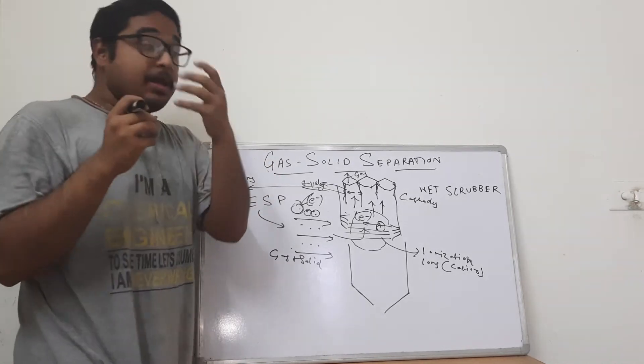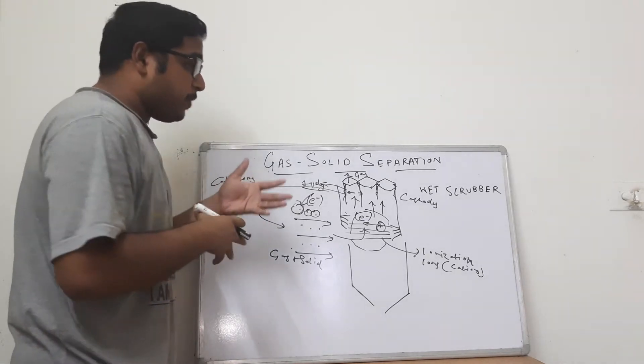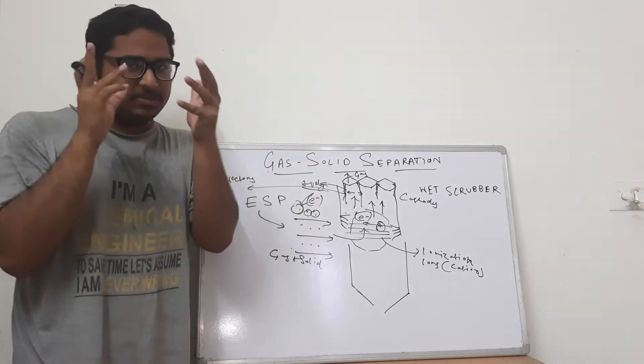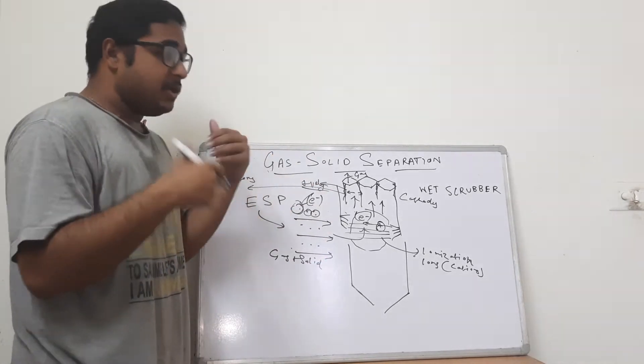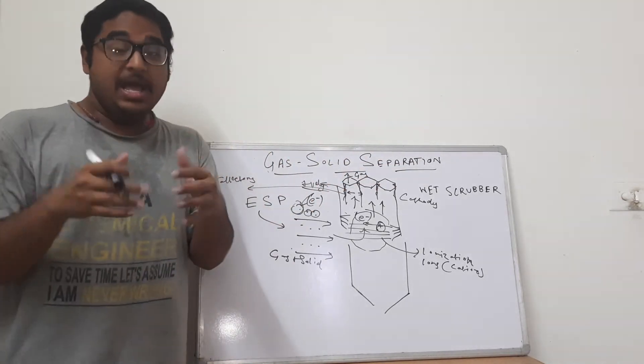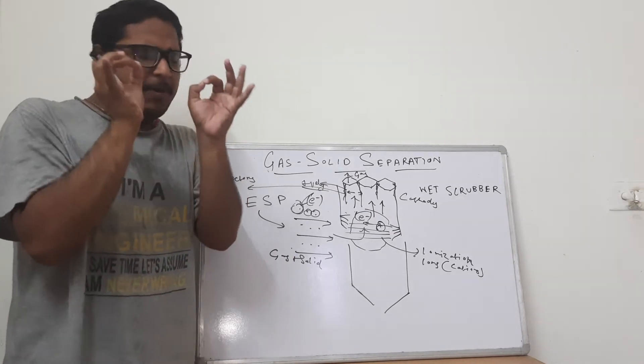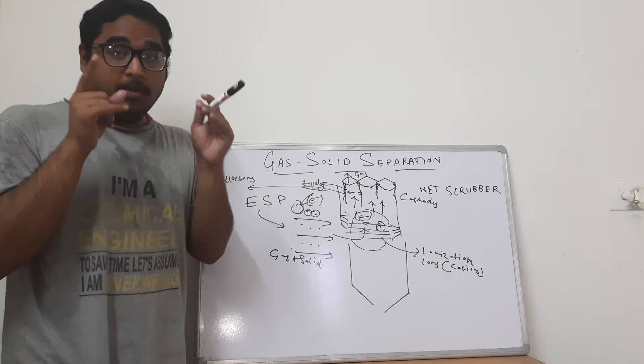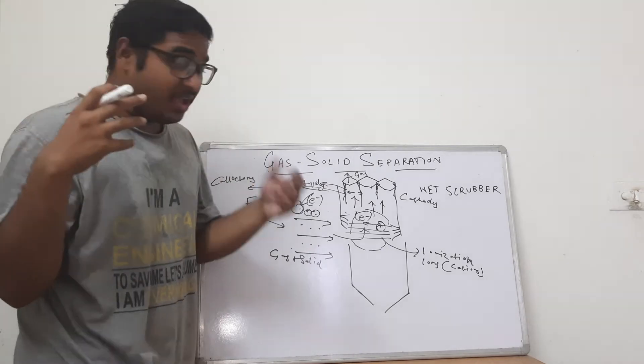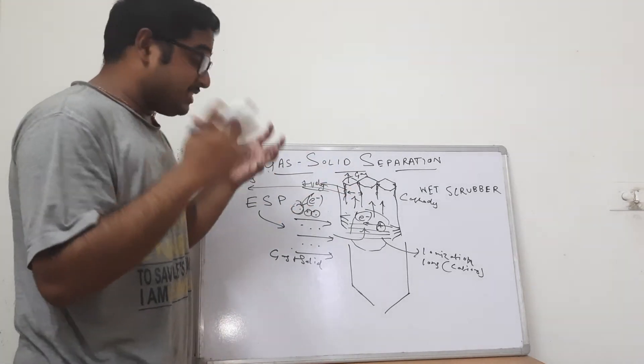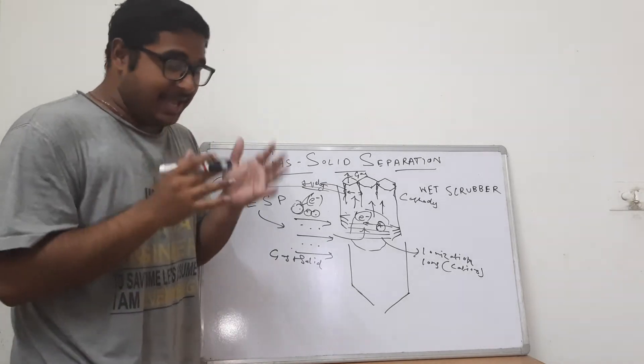Cyclone separators are used to separate relatively larger particles, whereas ESPs, wet scrubbers, and bag filters are used to separate very fine solids. The two systems we discussed earlier — bag filters and cyclone separators — handle relatively larger particles, and the two systems discussed today handle finer particles. Fine particles are trapped by this method. This is an expensive method because of the continuous electric field and the charge that needs to be maintained on the electrode surfaces.